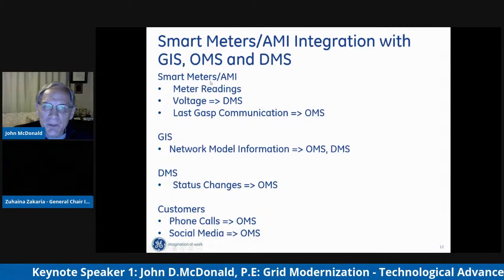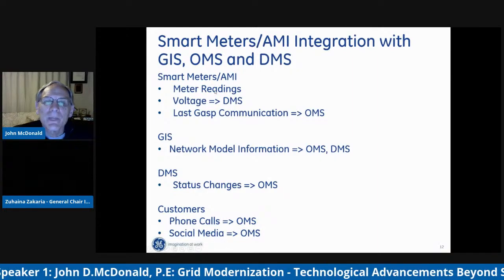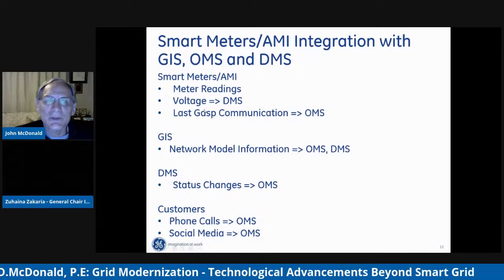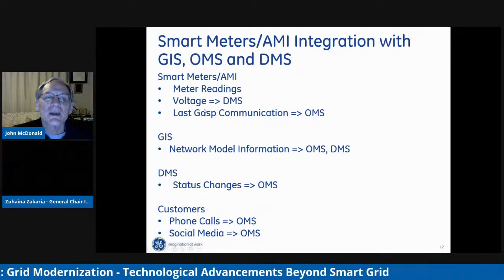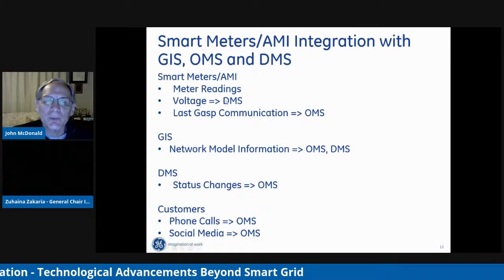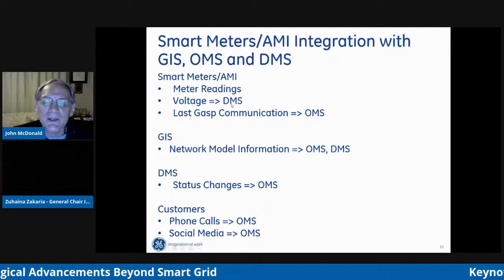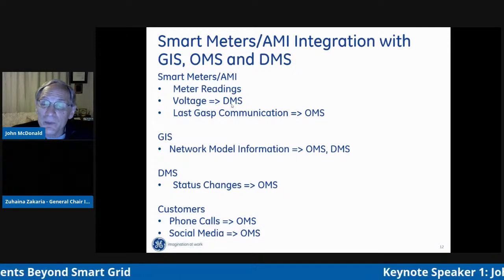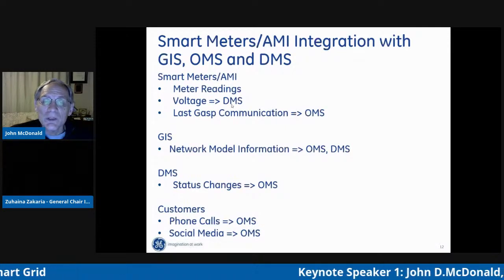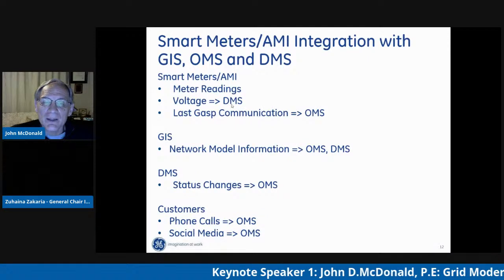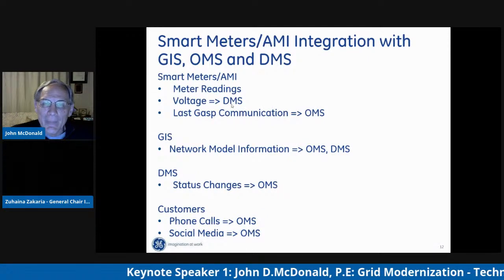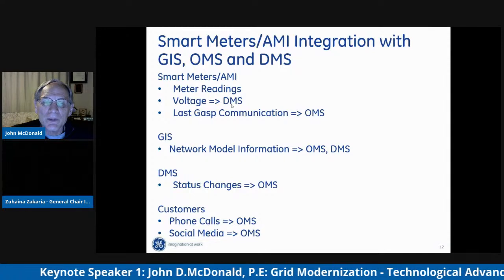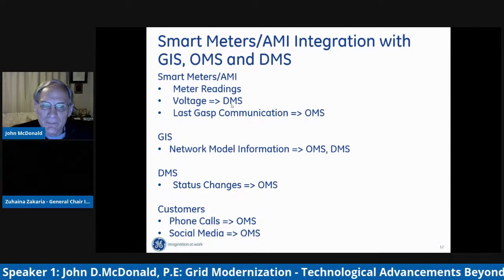As I mentioned with smart meters, in addition to meter readings, we will ping certain smart meters to get the voltage and bring that into the DMS network model. Why? When we do volt-var control, we need to make sure that the voltage at the customers at the end of the feeder is not below the minimum standard in our country.